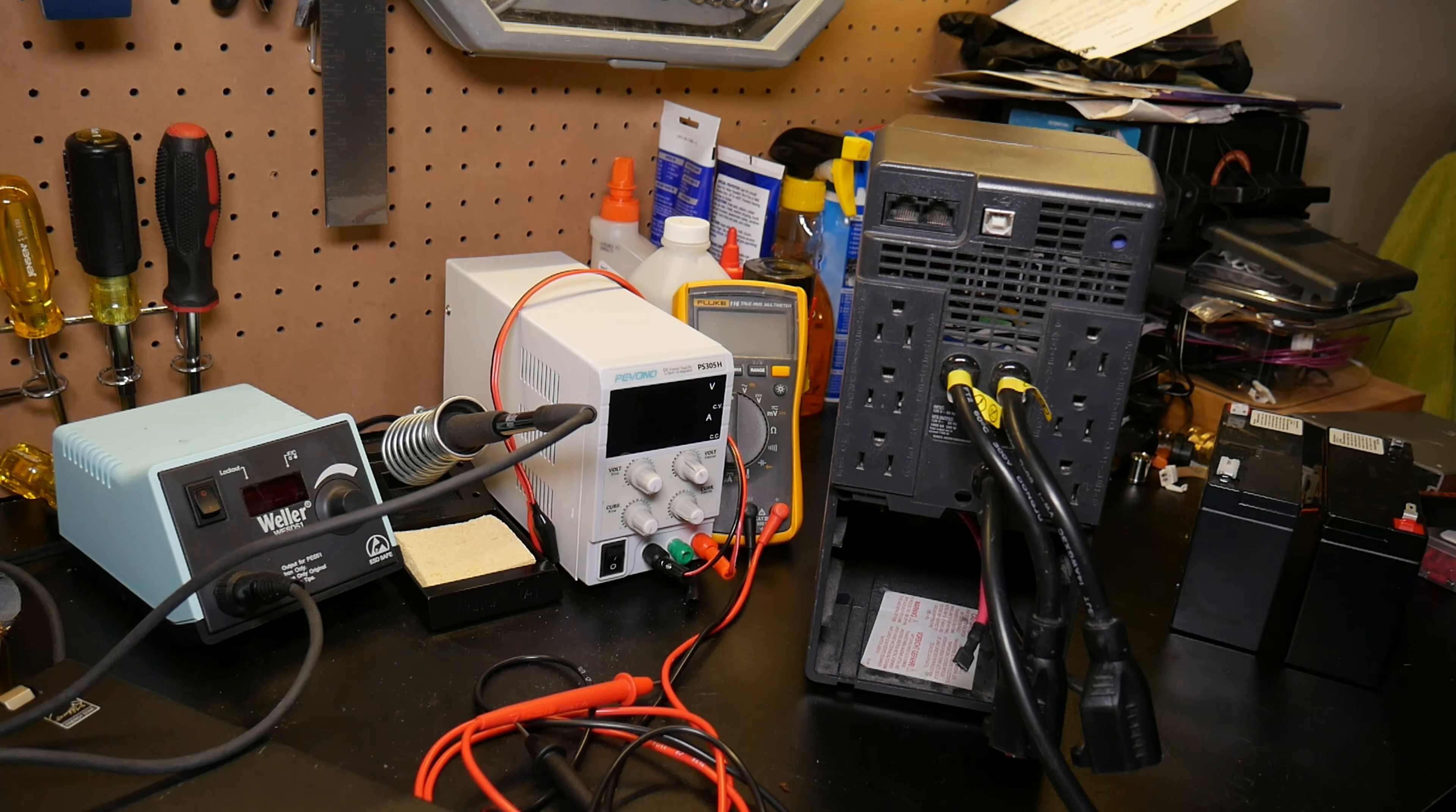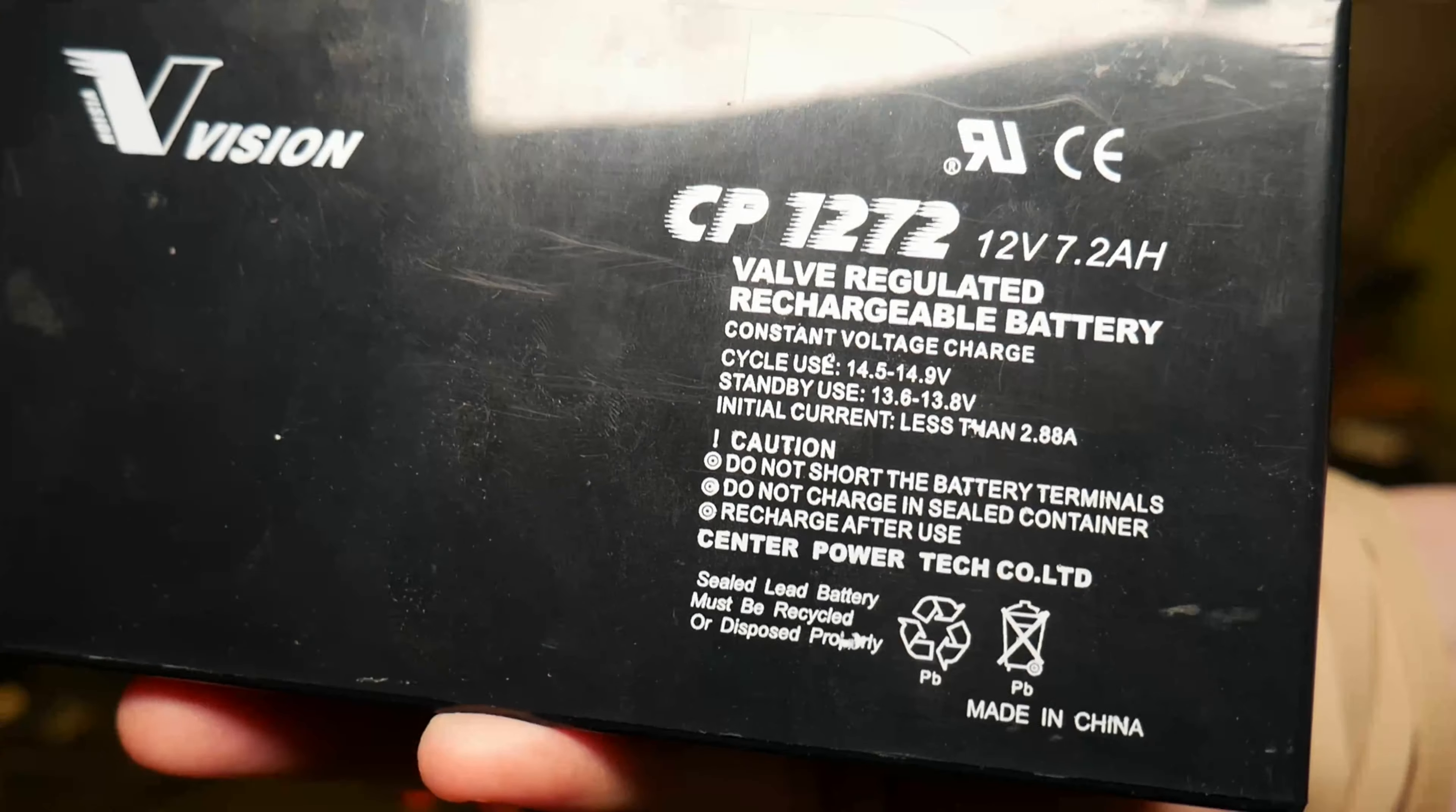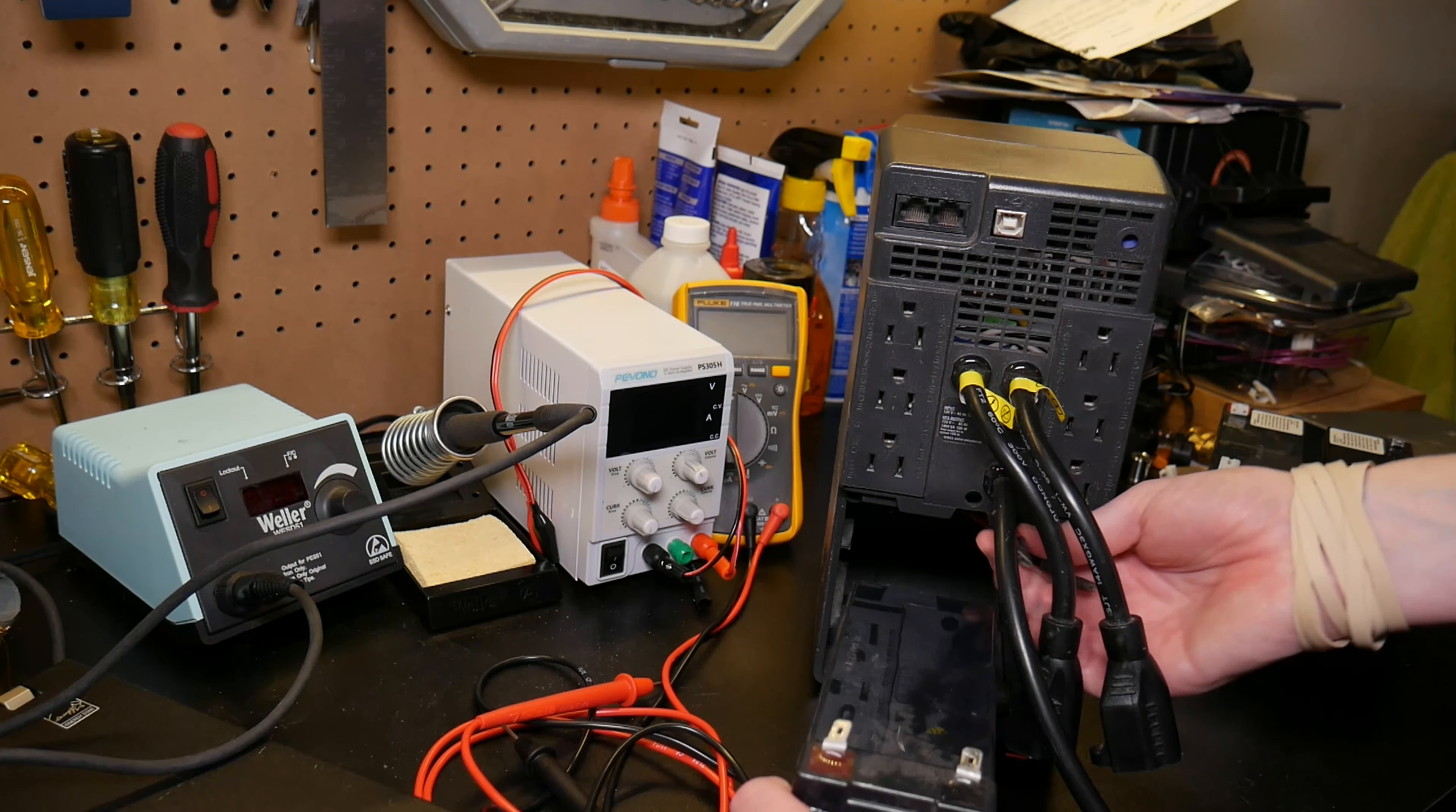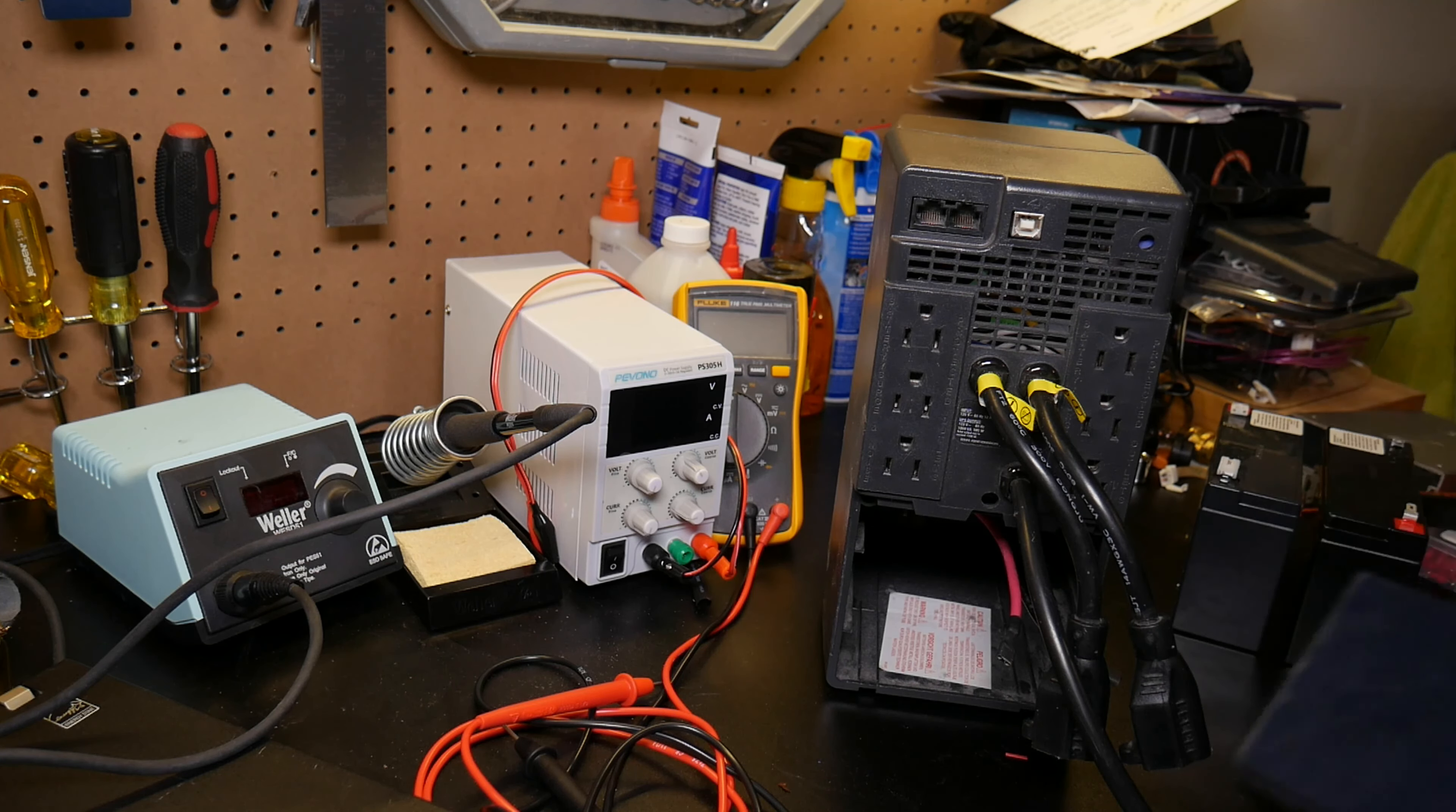The battery that was in here is actually the wrong one for this unit anyway. It's a 12 volt 7.2 amp hour sealed lead acid battery, but it isn't the right battery for this. The terminals never really fit properly and the capacity is obviously not as high as if I had the proper batteries for it.